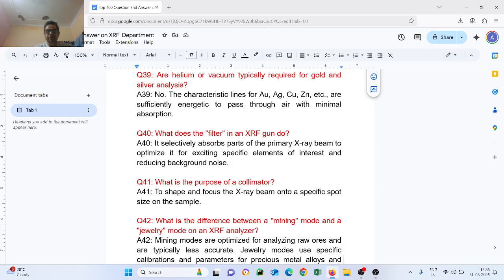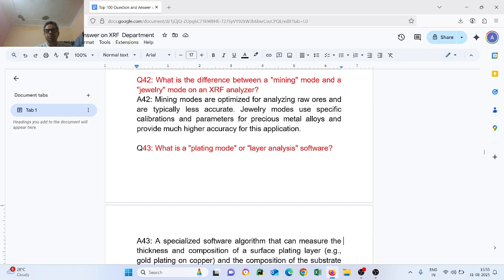What is the difference between mining mode and jewelry mode on the XRF analyzer? Mining mode is optimized for analyzing raw ores and is typically less accurate. Jewelry mode uses specific calibration and parameters for precious metal alloys and provides much higher accuracy for this application.